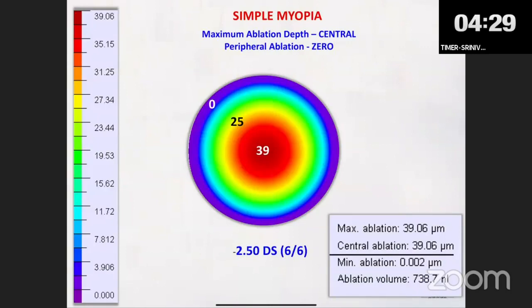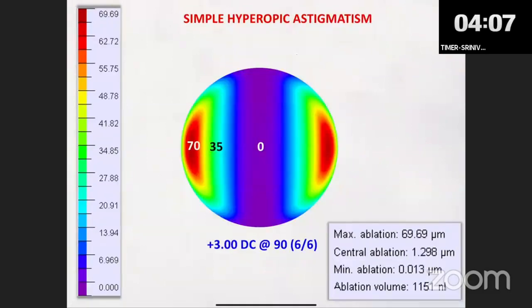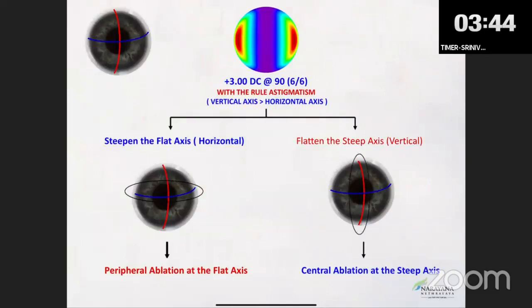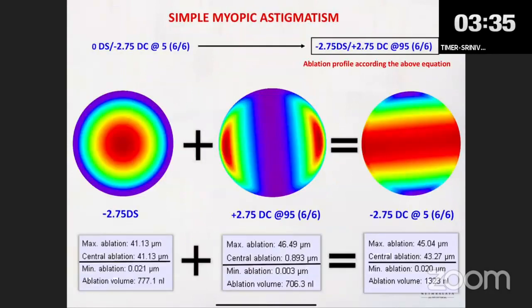How does laser surgery correct cylinder? All cylinders today are corrected on the plus cylinder axis. Even if you have a minus 3 at 180 degrees, the machine actually corrects it as plus 3 at 90 degrees. The laser ablates in the periphery on the weaker axis to make the flatter axis steeper. If you have a minus 2.75 at 5 degrees, the machine completely transposes — treating minus 2.75 sphere and plus 2.75 cylinder at 95 degrees.